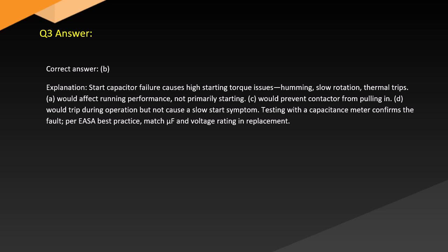Answer. Correct answer: B. Explanation. Start capacitor failure causes high starting torque issues: humming, slow rotation, thermal trips. A would affect running performance, not primarily starting. C would prevent the contactor from pulling in. D would trip during operation but not cause the slow start symptom. Testing with a capacitance meter confirms the fault. Per EASA best practice, match the microfarad and voltage rating in replacement.